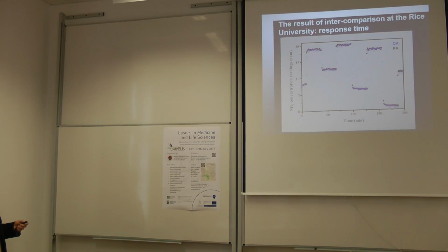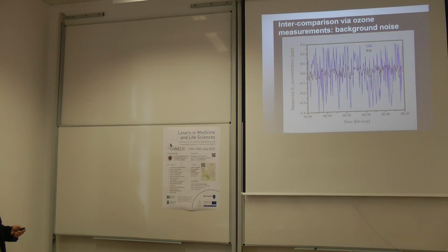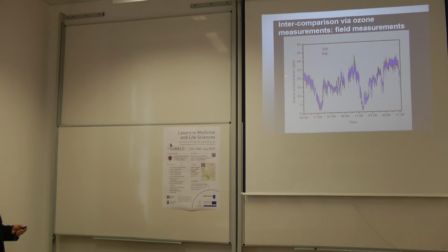I compared the photoacoustic system with the optical absorption system, and you can see that the photoacoustic, this black, is responding faster than the optical absorption system. If you compare the background noise of the two methods, you can see that the photoacoustic is less noisy, and otherwise they are giving very similar results.